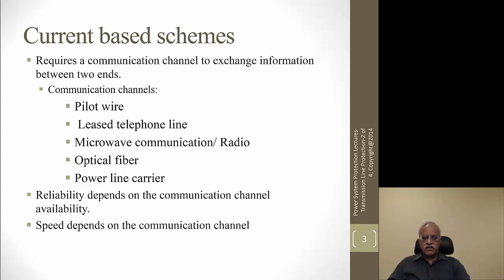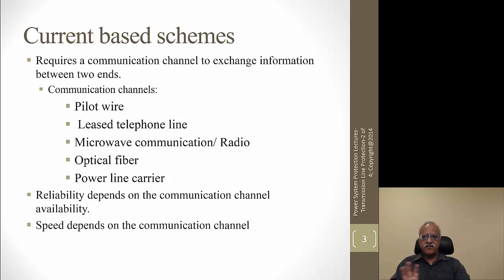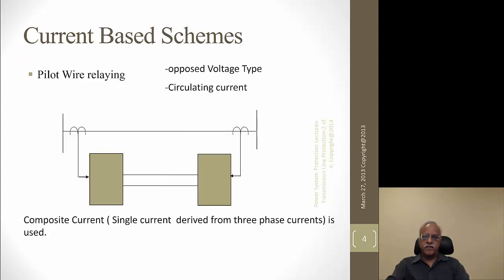The speed also depends on the communication channel. Fiber optics is very fast. Similarly, powerline carrier is very fast — within 3 to 5 milliseconds. Whereas a leased telephone line could take a cycle, around 16 milliseconds, to exchange information from point A to point B. The main focus of these lectures will be on distance relaying, which is the key topic. The rest are simpler concepts. Distance relays are a little more complex than the other schemes.